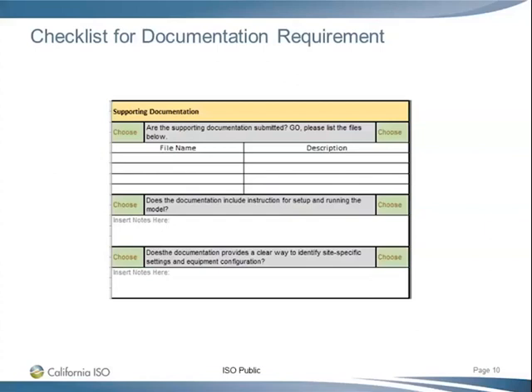Yeah, for MOD-026 and 027, you have field test results. So if the EMT model, the positive sequence model, and the field test don't all match up, then the field test data is the reference. The other two models should both produce results that are comparable to the field test. So it could be that either one could be wrong, either the EMT model or the positive sequence model.